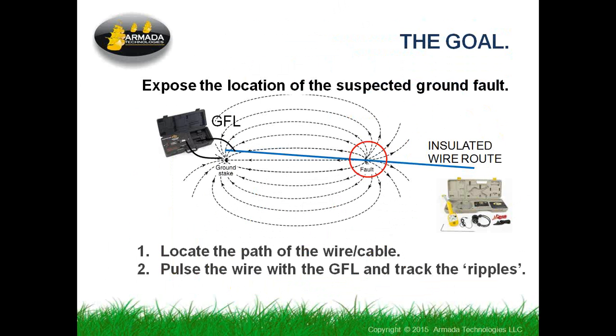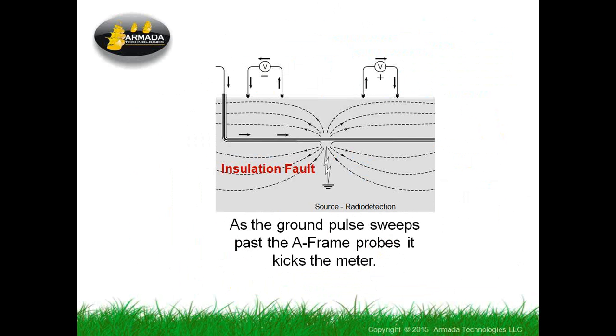It's important to kind of understand that underlying technology. So the ground pulse that we're providing here, this is an insulated cable normally, of course, which is what we're dealing with. If the insulation has been compromised, then it's open to the earth, and you put a high voltage pulse on it, and it causes a ripple, like a ripple in a pond, like a stone being dropped into water. And these ripples return to the ground stake, and we detect them by using the A-frame, which has two probes on it. It can tell what direction the ripples are passing from and going toward.